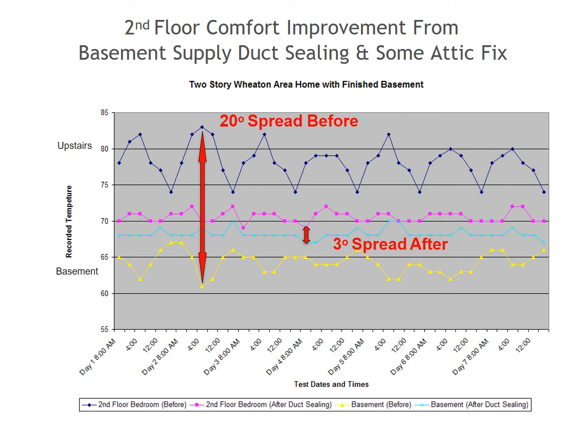Now, what I was referring to with the 20-point spread is the fact that at one point you had a 20-point spread between the upstairs and the downstairs. After the duct leakage was addressed, they were able to decrease it so it was only an average of about a 3-degree difference between the two. A huge dramatic improvement of the system just by fixing the ductwork.